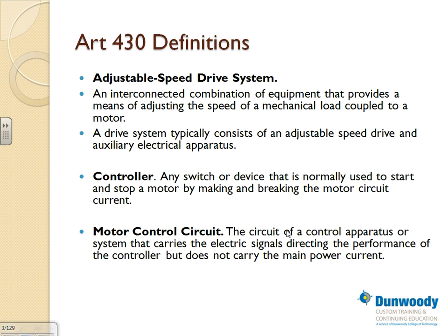So the two ways. The second one is the controller. With a controller, you can start and stop a motor. If it's a high-end controller like a VFD, you can ramp it up, ramp it down, and control it. If it's a low-end across-the-line controller, it could be as simple as a snap switch for a fan in a bathroom. That's a controller. The next step higher is a magnetic starter. You push a button, start, stop, and you start and stop the motor with no voltage reduction, no inrush reduction, no torque reduction. So that's a few things, guys, about the motor controller. Does everybody understand these terminologies, inrush over motor and all this good stuff?